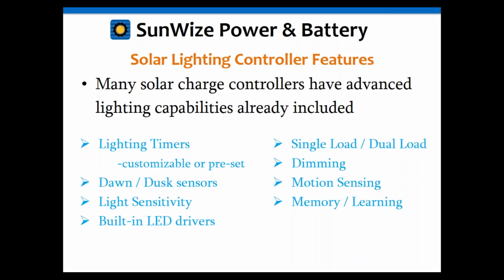So as Rob mentioned, most of the solar lighting charge controllers can perform multiple functions at once. They can act as both a solar charge controller and a lighting load controller simultaneously. Within these units, there is a pretty wide range of functionality and features specifically designed to control lighting loads. Some of those include lighting timers, which can be either customizable or preset from the factory, and dawn and dusk sensors, which utilize the solar array to tell the system when the sun is rising and setting. Then there's light sensitivity, which can be used to control the light threshold levels at which various lighting functions are triggered. This can be affected by things like light pollution, specific module selection, and other things.